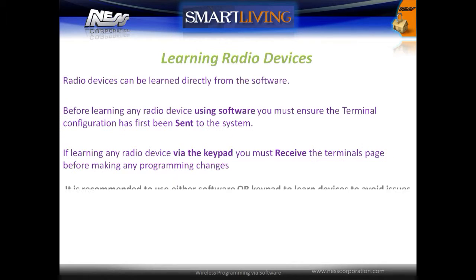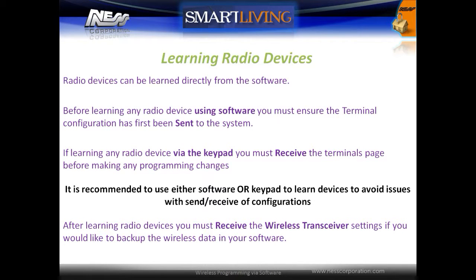Radio devices can be enrolled using the software. Before learning any radio devices using the software, you must ensure the terminals configuration has been sent to the system first. If devices are learned via the keypad, the terminals page must be received before making any programming changes. It is recommended to use either the software or the keypad to learn devices to avoid issues with sending and receiving configurations. After learning any radio device, you must receive the wireless transceiver settings if you would like to back up your wireless transceiver data.